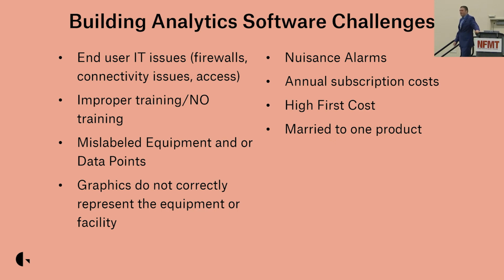You'll look at the graphics and find that the person who put them together doesn't actually know your building. They'll have pumps wrongly oriented with the chiller, maybe pulling out of it instead of pushing in, or vice versa. The point is, a lot of times they haven't paid enough attention to what they're showing you on the graphics, which can be misleading and lead you to the wrong conclusions. The graphics just don't represent the equipment in the facility.